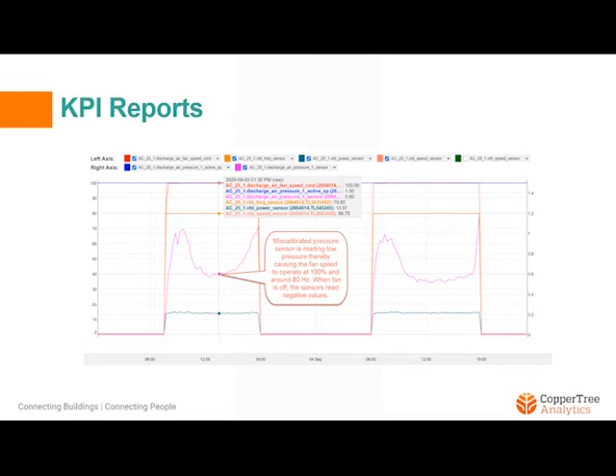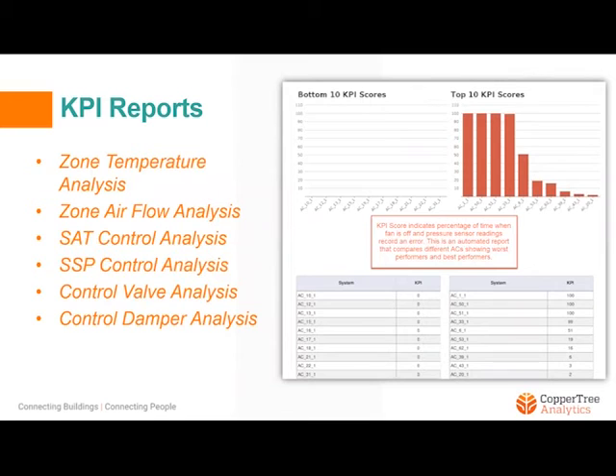All because a pressure sensor is reading inaccurate readings. Now, this building, which is a high-rise, has 65 ACUs in the building, 1 ACU per floor. In the KPI reporting slide that I have here, I'm showing you how a KPI report was used to capture poor performing systems. The KPI score here indicates percentage of time when the fan was off and the pressure sensor readings recorded an error. It's an automated report that compares different ACs, showing worst performers and best performers.